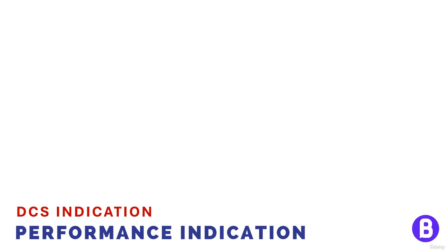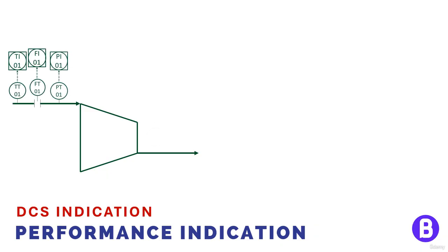For a compressor, as the compressor is so sensitive to the fluid inlet flow, pressure, and temperature, it's common to add instruments measuring the flow, pressure, and temperature on both compressor suction and discharge. These are not just used for indication, but for control and shutdown of the compressor, as the compressor needs complicated logic solvers. This is related to compressor anti-surge control. I have talked about anti-surge in the compressor course. You can check it out in the bonus section if you like.